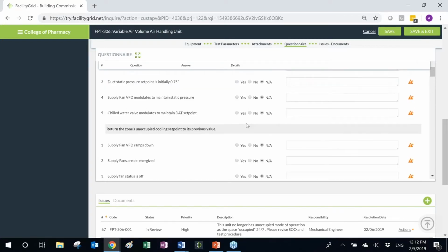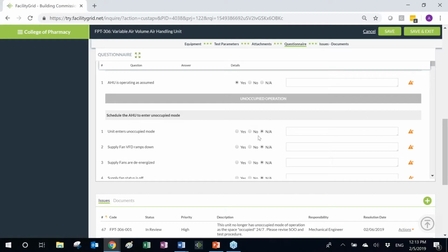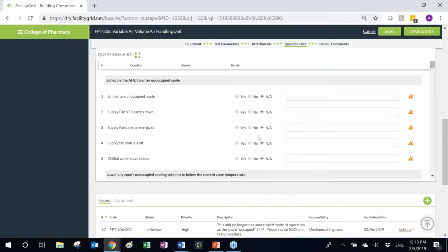Now, I may also come to a section, in this case unoccupied operation, where I know as a controls contractor that this particular sequence of operation is not applicable to this equipment, because this equipment happens to operate 24/7. It does not have an unoccupied mode. So I'm going to indicate my response as non-applicable, and then I'm going to simply click on this issues icon, which is the triangle, and create an issue. You can see that Facility Grid automatically copies the text from that particular question into the description of the issue.